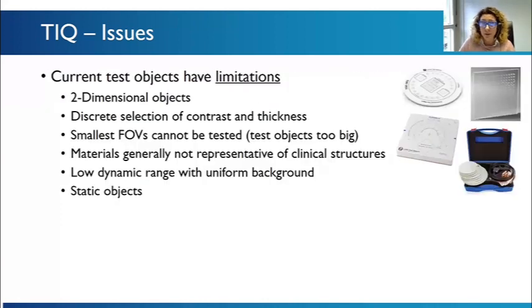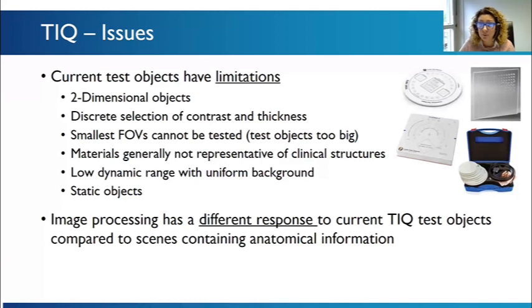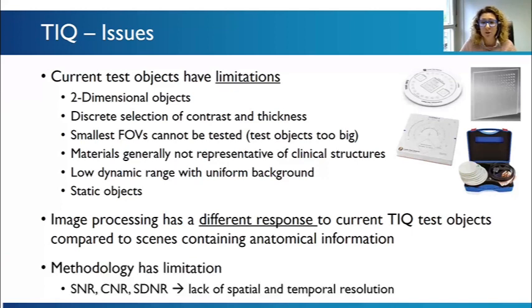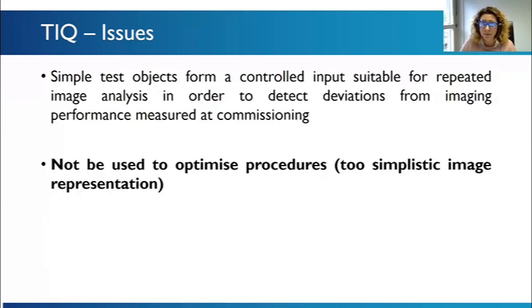These objects currently have limitations. They are mostly 2D objects. They are static objects. They are large, so the smallest field of view cannot be tested. Contrast and thickness don't vary continuously, but in a discrete way. Materials are not representative of clinical structures, and that means the image processing has a different response to these test objects compared to anatomical scenes. And also the methodology has its own limitations, because there's a lack of spatial and temporal resolution, and we are supposed to test dynamic images. These are good because they can give us a control input suitable for repeated image analysis, but definitely they cannot be used to optimize procedures.